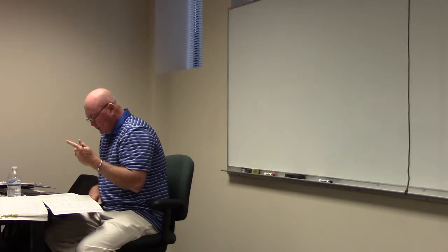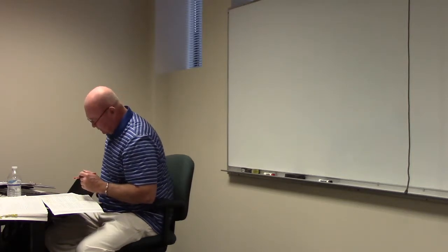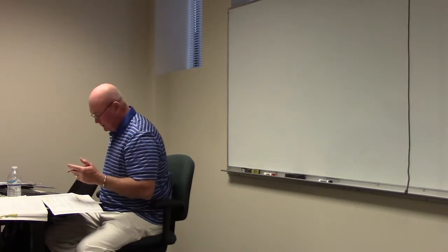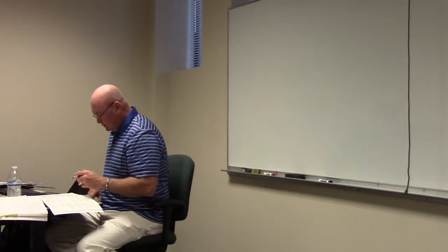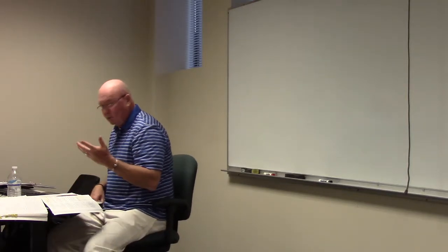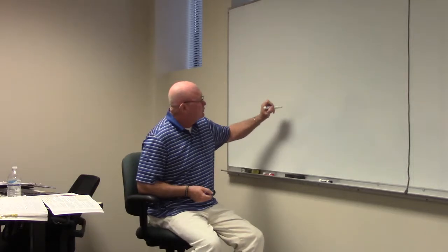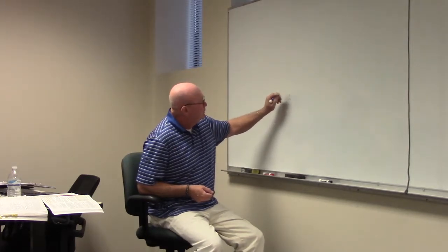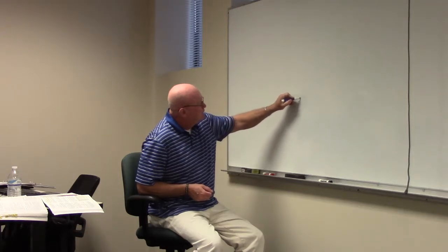At the school, it tells us the school has a 200,000 square foot floor area with a 480/277 volt service. Let's look at our loads. The interior lighting is already given to us. Our lighting is 600,000 volt-amps, because it's 3 volt-amps per square foot. That's our lighting.